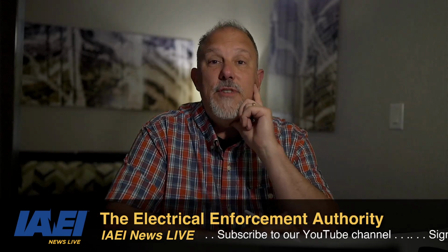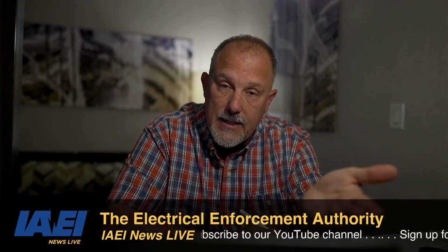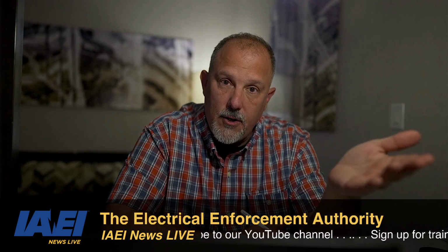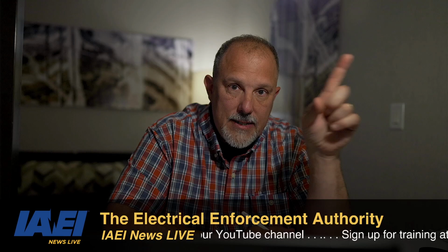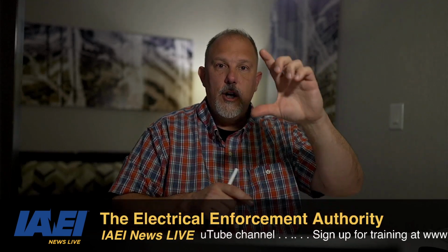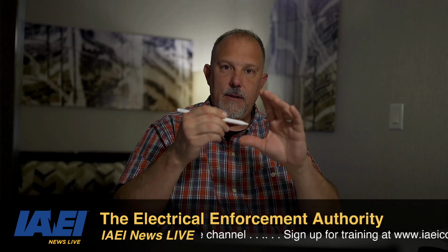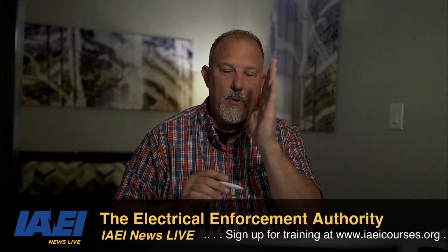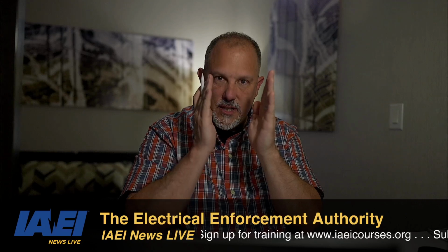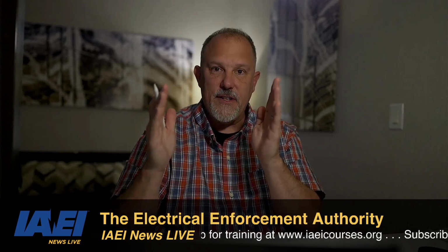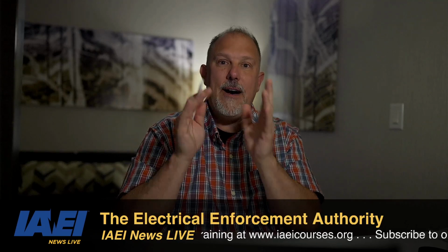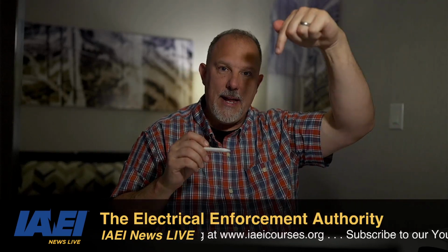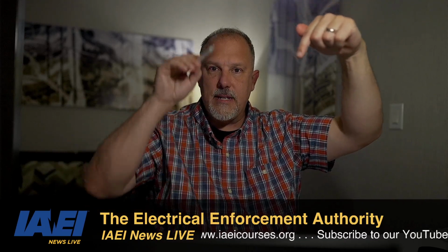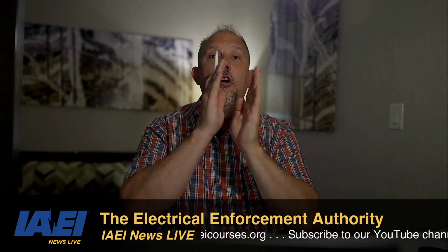Now, where might you see that? A good example on DC systems. They take a circuit breaker, one circuit breaker, and they take the one conductor and they wire the poles. So you have A to B, say you have A, B, C, D, E, F. A to D is one pole. B to E is the second pole. C to F is the third pole. They'll tell you how to wire that so that you come in on A, come out on F, and you basically serpentine the circuit so that you have 3 poles stopping the flow of DC current.